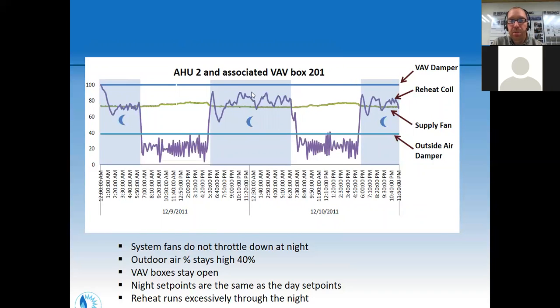The VAV damper, the variable air volume damper, is constantly at the same level. This should vary through the day and night, but it's just constantly at 100% full open. Imagine sitting in your office with the air damper over your head fully open, blowing cold air at you the whole time - there's a reheat coil there to reheat that air. This was causing an uncomfortable situation for the building, and it was reversed too, reheating more at night than during the day.